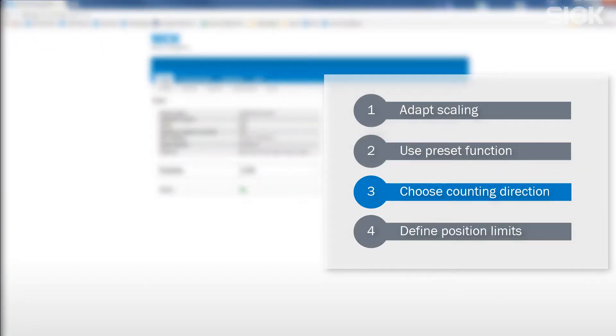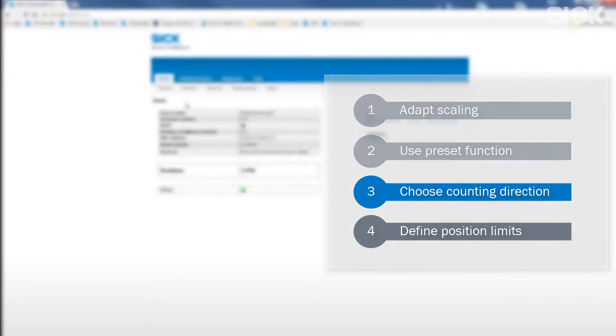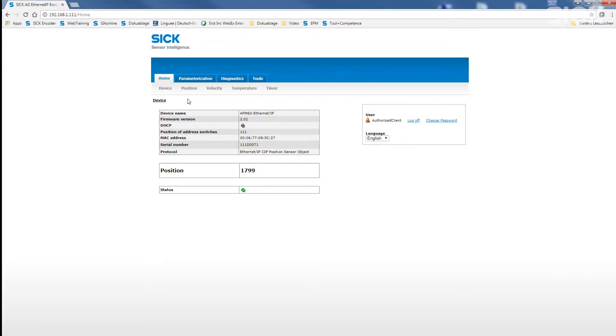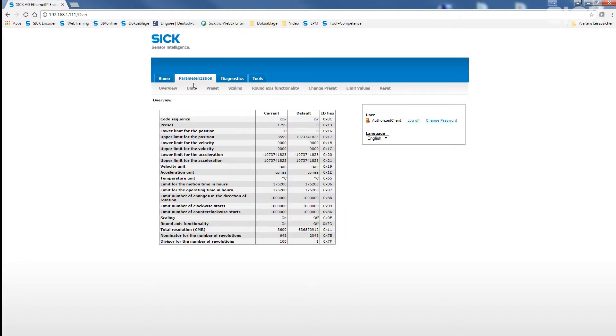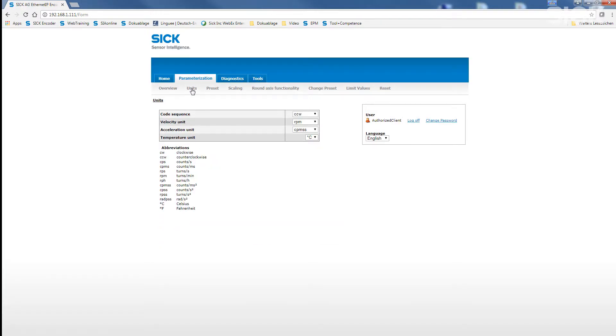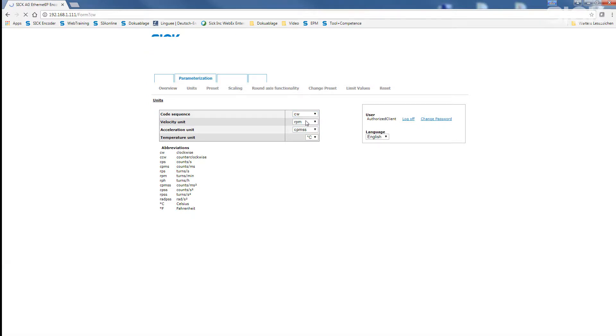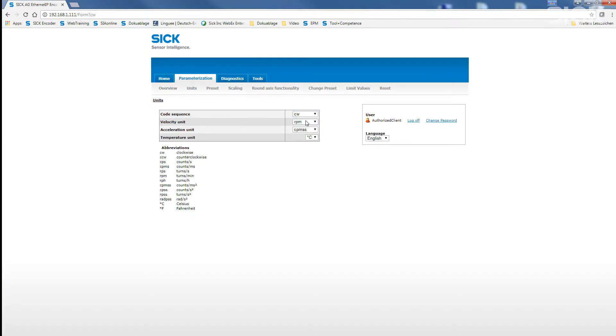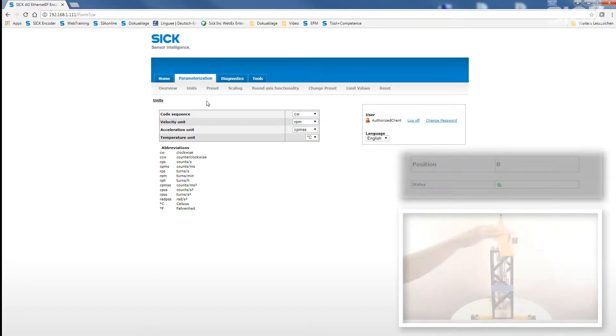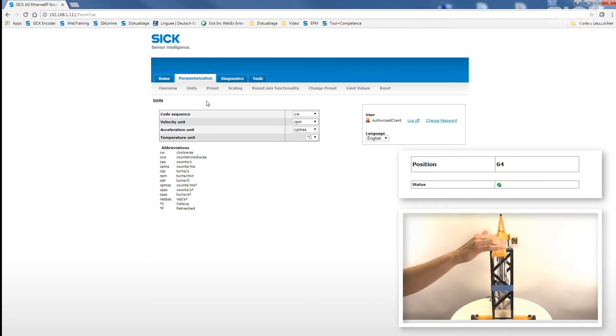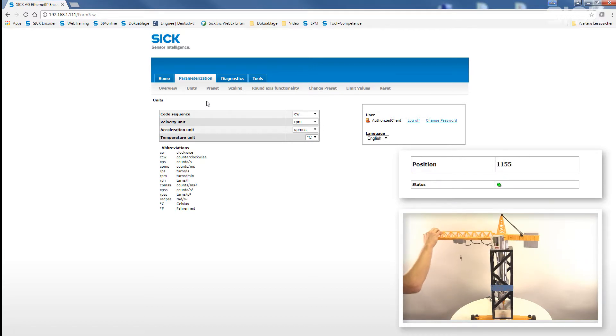Now, we need to check and adjust the correct counting direction. By using the submenu units, we can adjust the so-called code sequence to CW, meaning clockwise. This leads to rising position values when turning the encoder shaft in clockwise direction.